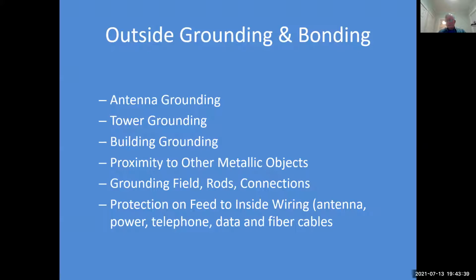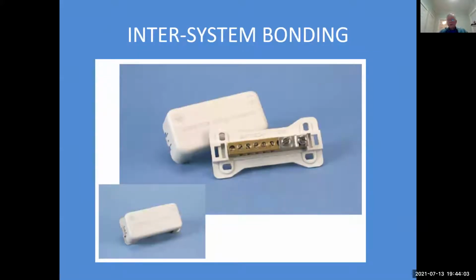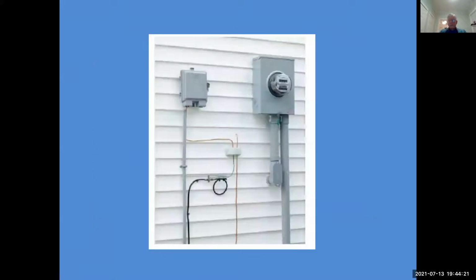What's really key is you want to make sure for every conductive path into your house, whether it's your antenna, power, telephone, data, fiber cables, unless they're full dielectric fiber, they may have a metallic component inside. So you want to eliminate any path that will easily provide a way for any surges to come into your structure. And the so-called intersystem bonding device, this is one example that's called for in some of the code requirements, where you connect this device to your ground electrode conductor, and then you can tie all your other systems to the other ports on the bar.